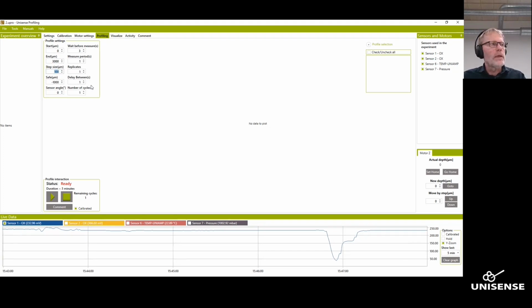The step size, so a profile consists of moving the sensor, stopping it, waiting some time, and then recording a data point and then move on. And the step size here I want to start with is, let's say we start with 200 micrometers, so 5 measurements per millimeter. The safe distance is the position the sensor will be pulled out to when the profile has finished. So that's nice if you leave it to work on its own and go away for coffee, then the sensor will be taken out to a safe position.